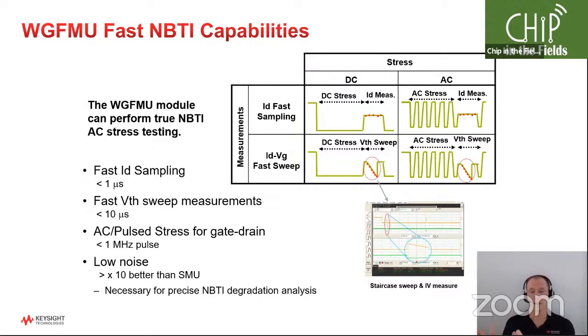Now, it could be a simple spot measurement, as shown in the top right of my diagram. I can even do a sweep measurement if I wanted to, for example, do a very quick sweep measurement from stress and go right back into stress without having any kind of glitching. So my device definitely keeps its stress and it's not going to relax and go back to its normal state. It can do very fast sampling, less than a microsecond, and it's got a lot better noise capabilities than SMUs, of course, have. So again, very good solution, very good tool for doing these types of fast measurements.